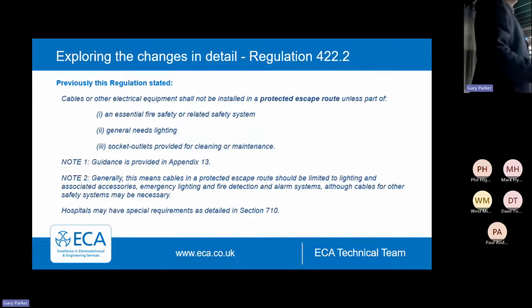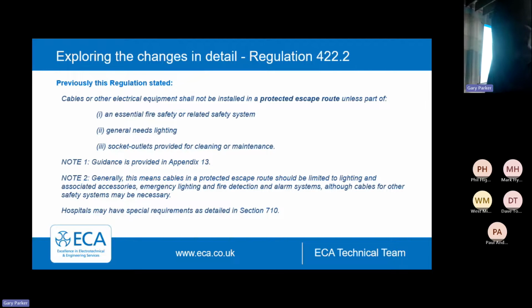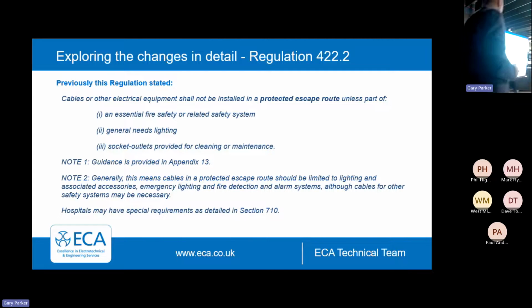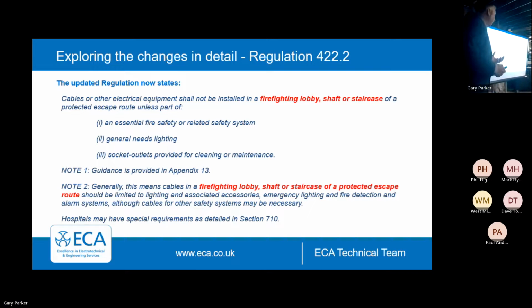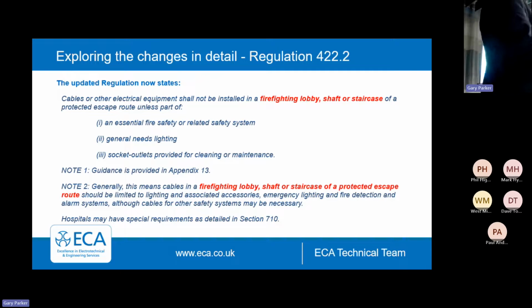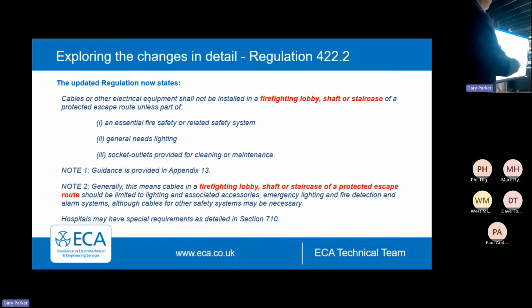However, this threw up a lot of problems, especially in larger projects. So they changed it to emphasize that cables or electrical equipment shall not be installed in a firefighting lobby, shaft, or staircase. They've linked it to BS 9999 and nabbed a few phrases from 8519 as well, talking about firefighting lobbies, shafts, or staircases.